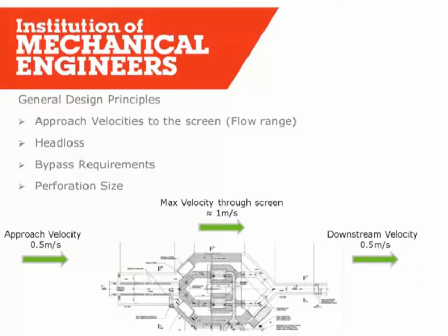On head loss: Rob will touch on this later, but you need to assess the screen in both its clean and dirty head loss conditions. There are different ways of doing that and manufacturers will have their own approaches. Always be aware that you need to consider both options. Bypass requirements: it is always good practice to have a bypass on your inlet screens because at some point they will blind or fail - that's not a possibility, it's a given. On your bypass you need to be able to pass full flow and ideally screen it, perhaps with a 50mm bar screen, which would typically be manual. Perforation size is sometimes dictated by the environmental permit but can be made tighter by downstream process constraints - for example, a membrane bioreactor may require screening down to three millimeters in two dimensions.